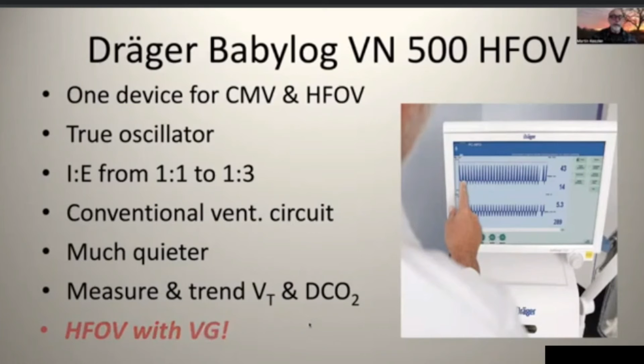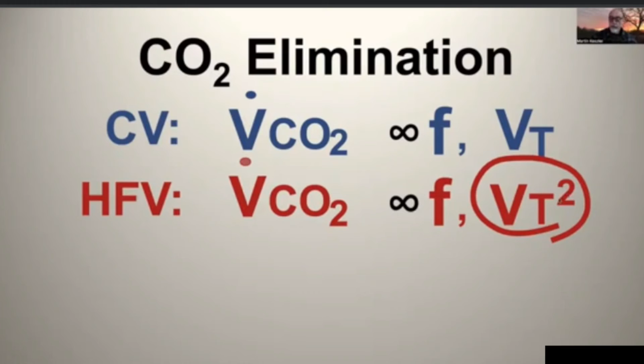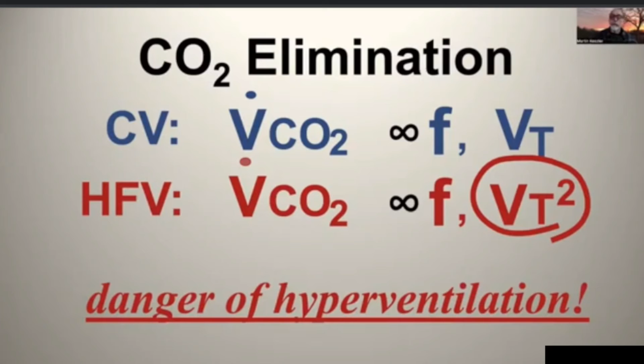Why is it important to be able to use volume guarantee with high frequency? You remember that CO2 elimination with conventional ventilation is proportional to frequency or rate and tidal volume. With high frequency, it is frequency and tidal volume squared. So tidal volume is a much more important factor, and even small changes in tidal volume can readily alter CO2 quite dramatically, and there's a real danger of hyperventilation, and that's been shown in a number of different studies. So that's some art in there. How does it work? Well, for those of you not familiar with it, it really works rather like conventional volume guarantee.